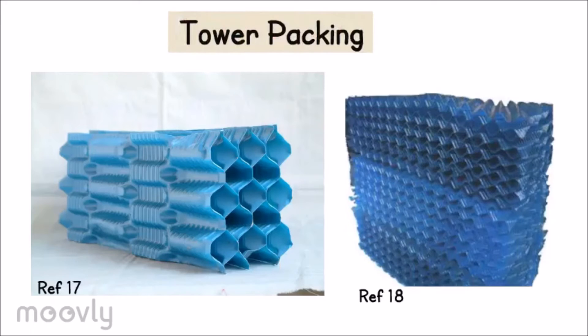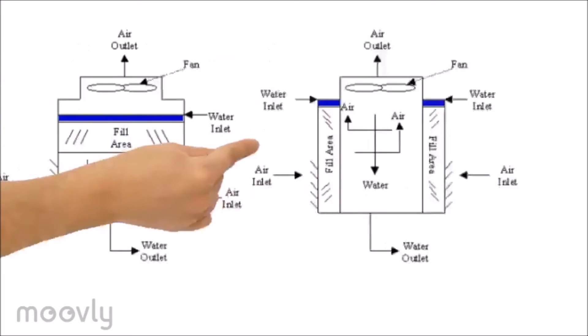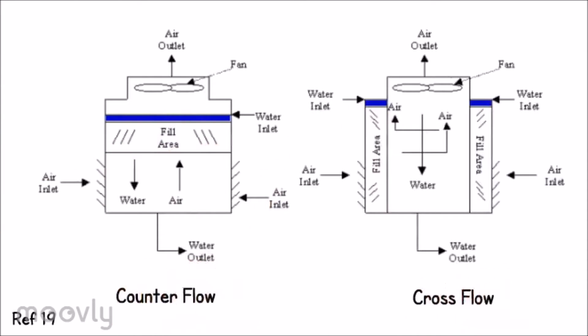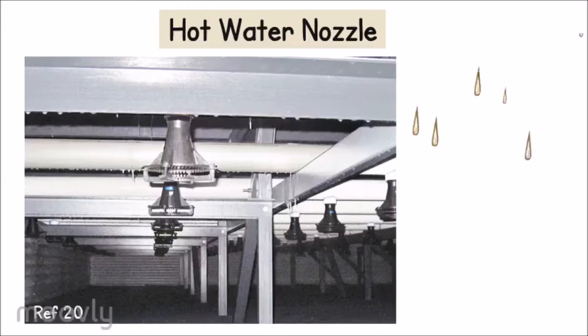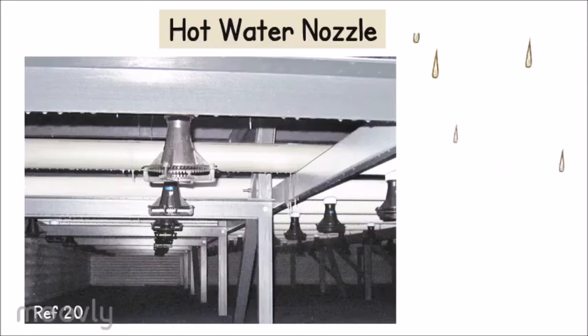Tower packing consists of plastic material and provides a large contact surface area between the hot water and air for a more efficient heat-removing process. The orientation of tower packing depends on the flow of fluid inside the cooling tower — counter-current or cross-flow fluid movement. Hot water nozzles aid in spraying the hot water onto the tower packing in the form of small droplets in order to achieve a bigger contact area with the incoming air.